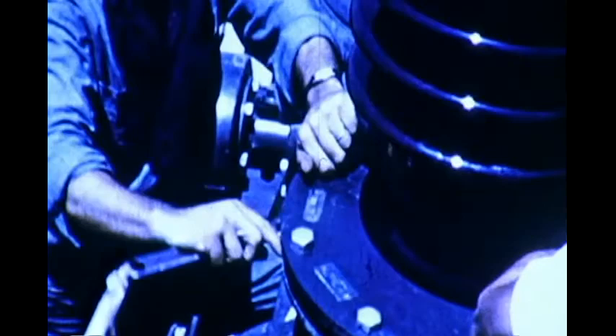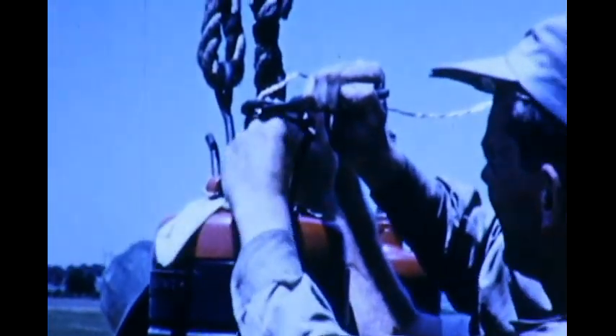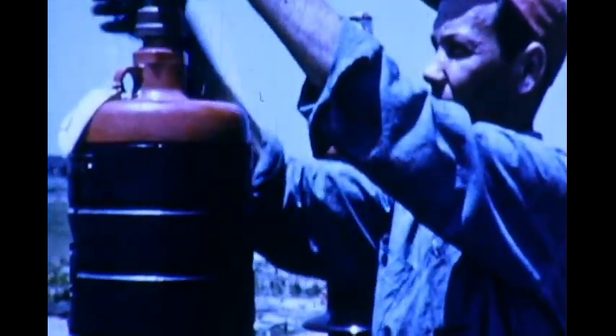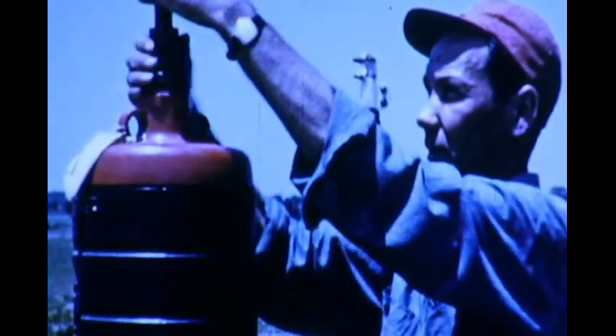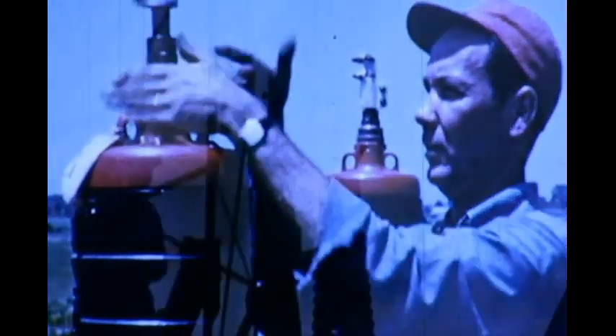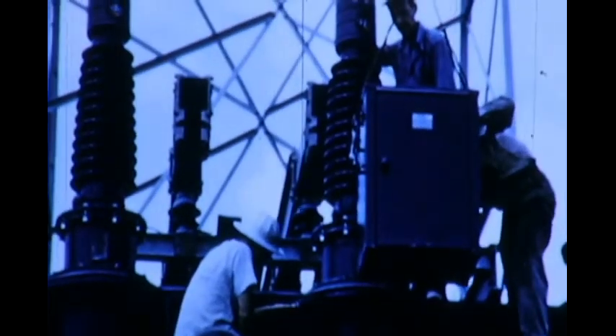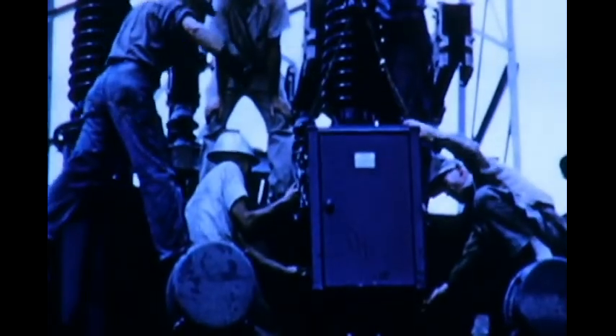The bushing is bolted progressively in one direction until all bolts are uniformly tight. The high voltage lead is secured by a small pin, after which the bushing terminal cap is added. A potential device is used to operate relays, voltmeters, and other instruments with a capacitance tap on the high voltage bushing providing the necessary power. With this job done, we are ready now to install the low voltage bushings.